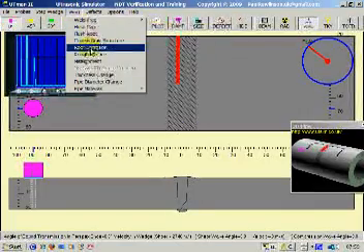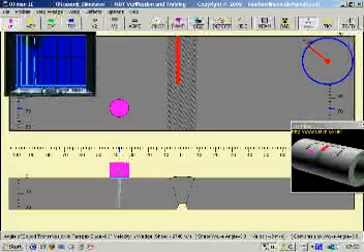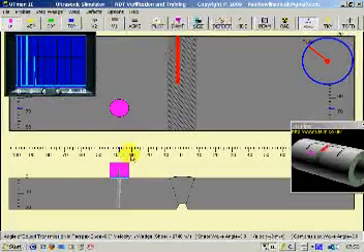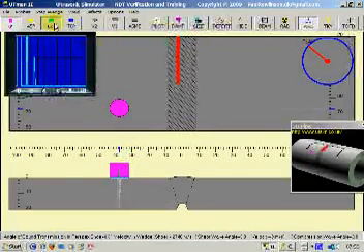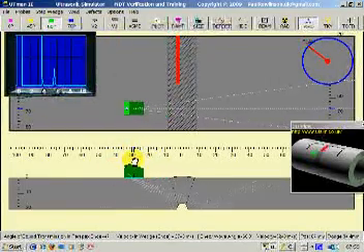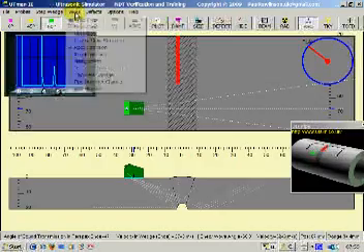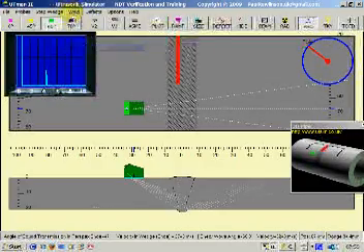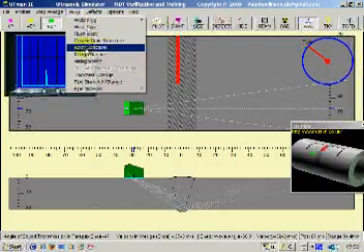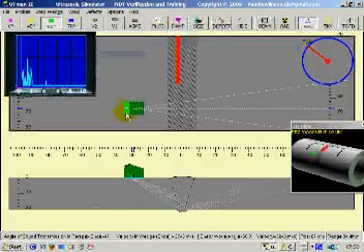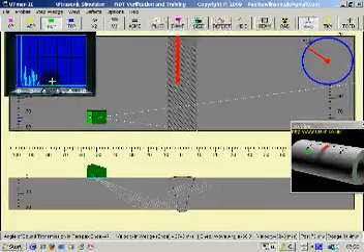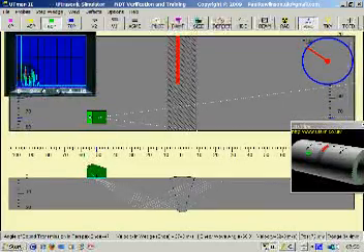Compound bevel. We could have root corrosion. We could have a rough surface of the pipe, which gives us a lot more noise on the A-scan.